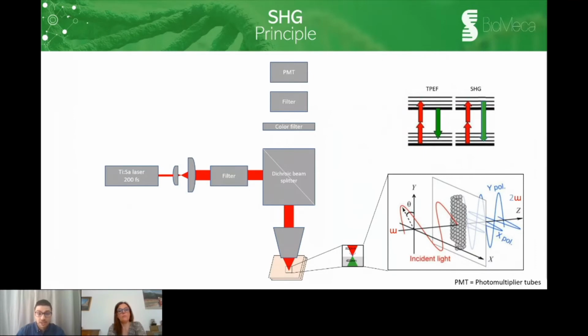This signal comes from two excited photons which interact with the material, and then a new photon with half of the wavelength is emitted. It is a two-photon process, but unlike TPEF, SHG is energy conserving, which means it doesn't involve exciting molecules. For example, with this setup, the Ti:Sapphire laser generates a beam at, for example, 800 nanometers. This beam crosses a telescope and its diameter increases. Then it hits the dichroic beam splitter, crosses the lens, and interacts with a non-centrosymmetric sample, which emits light at 400 nanometers wavelength. This is half of the wavelength entering the sample, which means that the frequency doubles. And this is the second harmonic light.